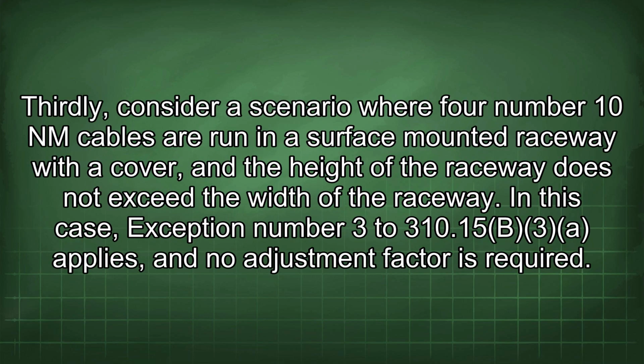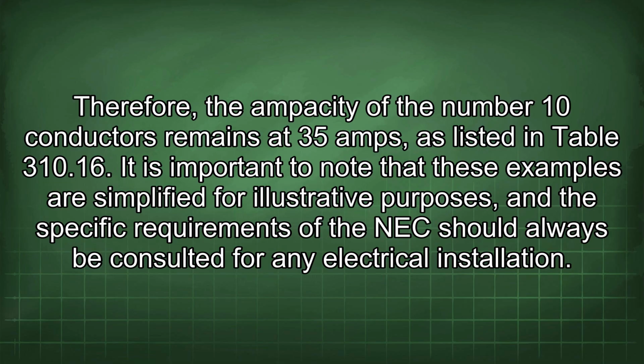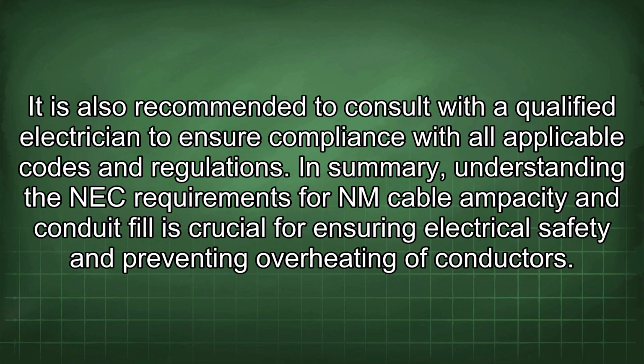Thirdly, consider a scenario where 4 number 10 NM cables are run in a surface-mounted raceway with a cover, and the height of the raceway does not exceed the width of the raceway. In this case, exception number 3 to 310.15(b)(3) applies, and no adjustment factor is required. Therefore, the ampacity of the number 10 conductors remains at 35 amps, as listed in Table 310.16. It is important to note that these examples are simplified for illustrative purposes, and the specific requirements of the NEC should always be consulted for any electrical installation. It is also recommended to consult with a qualified electrician to ensure compliance with all applicable codes and regulations.